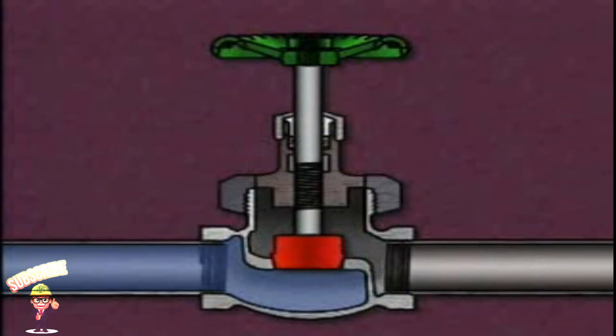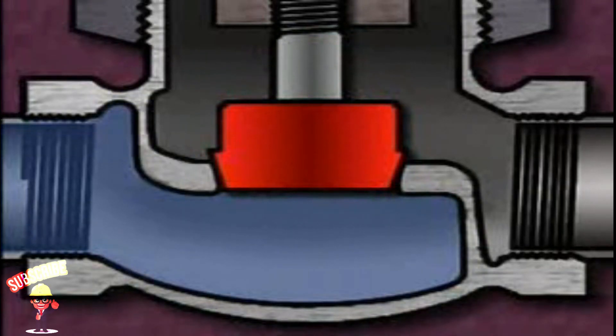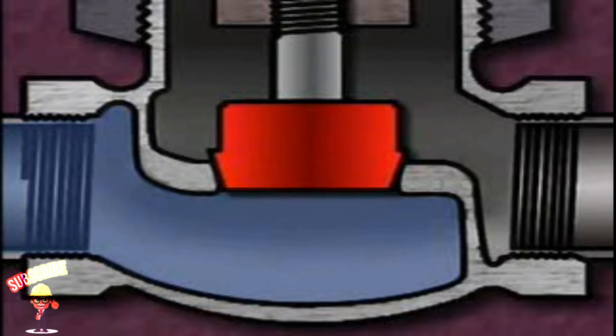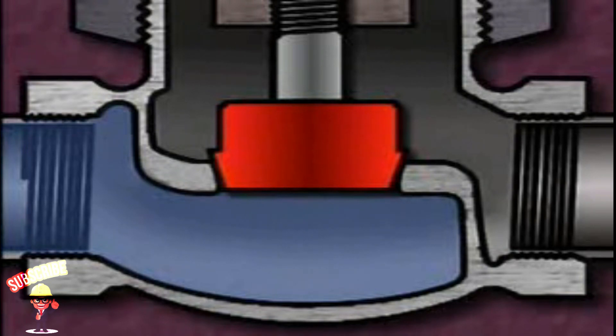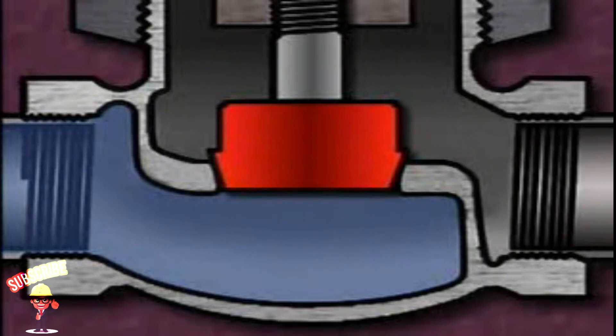Several different types of discs are commonly used in globe valves. A standard or conventional type disc seats against a tapered, flat-surfaced seat. A globe valve with this type of disc is generally used in either the fully open or the fully closed position, though it can also be used for moderate throttling or regulating of flow. Globe valves with conventional discs are normally used in low-pressure, low-temperature systems.